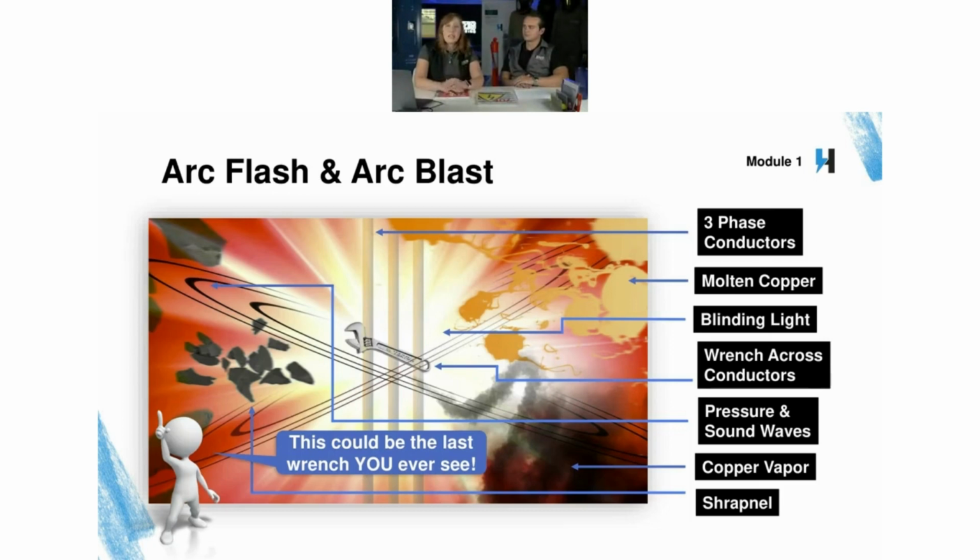It depends on your system, though, your situation specifically. One of the main things that the 70E talks about as far as arc blast hazard would be if you have a lot of capacitance in the system. The discharge of that capacitive discharge. Yes, that capacitive. I said it backwards. The capacitive discharge in an arc flash event can cause those extremely significant pressure waves and concussive shock waves, and it creates lung protection issues and all sorts of stuff. So that could be a potential if you have that in your system.